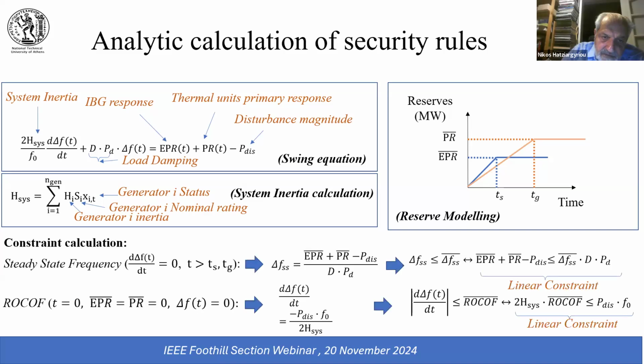Based on this equation, you can easily calculate the basic parameters that define the frequency behavior. One of them is the steady state frequency, which means that after the disturbance stabilizes, delta f over dt is 0. So at the time after TS and TG, you can assume that you have exhausted your reserves. Based on that, you can find the steady state frequency, which can be linearized and used as a linear constraint of your unit commitment problem.